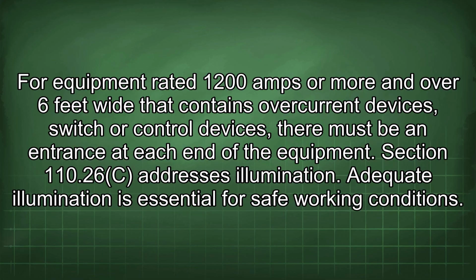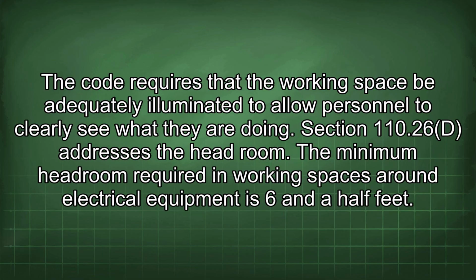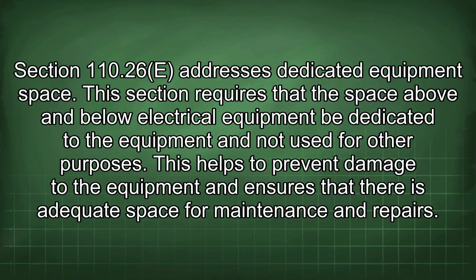Section 110.26(C) addresses illumination. Adequate illumination is essential for safe working conditions. The code requires that the working space be adequately illuminated to allow personnel to clearly see what they are doing. Section 110.26(D) addresses the headroom. The minimum headroom required in working spaces around electrical equipment is 6.5 feet. Section 110.26(E) addresses dedicated equipment space. This section requires that the space above and below electrical equipment be dedicated to the equipment and not used for other purposes. This helps to prevent damage to the equipment and ensures that there is adequate space for maintenance and repairs.